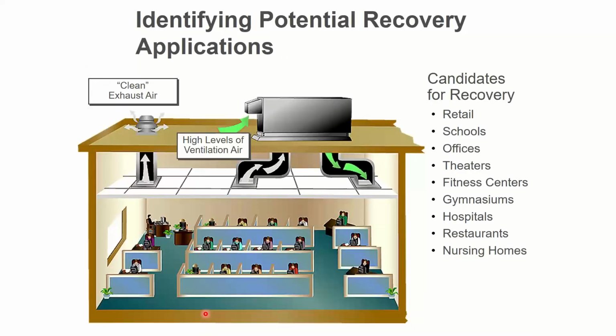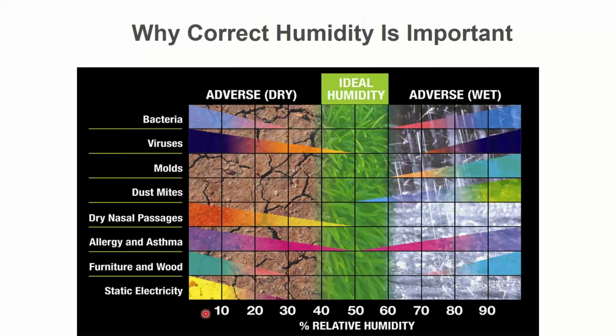Candidates for putting an ERV in, unless it's code required, obviously you got to do it. But if it's not code required, places you might want to do it are places that have a lot of people. Because places that have a lot of people have a lot of outside air requirement, and a lot of outside air and a lot of exhaust air are needed in order for an ERV to make sense. So movie theaters, gymnasiums, hospitals, these are the kind of places that have large amounts of outside air. So I want to have those places be the ones with the ERVs.